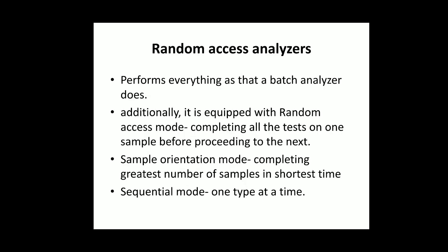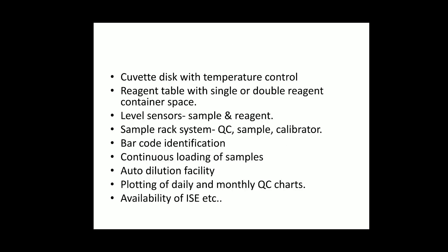The random access analyzer completes all tests of one sample before proceeding to the next — this is called random access mode. A sample orientation mode is also available, allowing a greater number of samples in a shorter time. A sequential type — one type at a time — is also available. All these features are present in the fully auto analyzer.